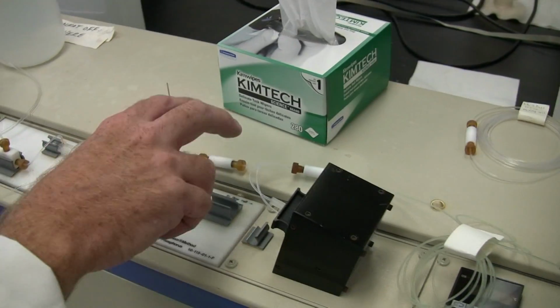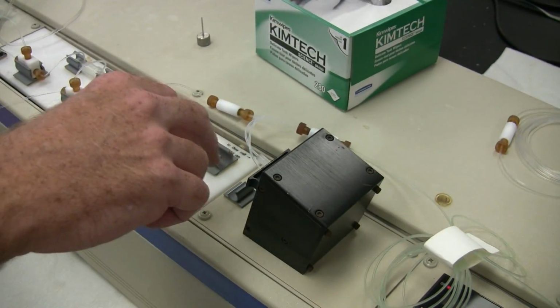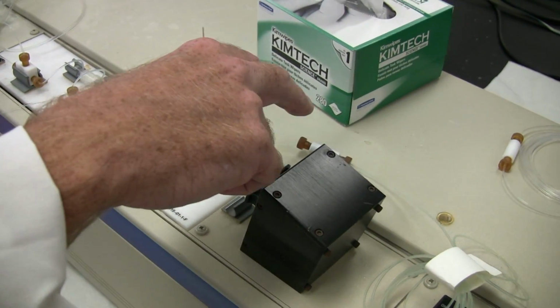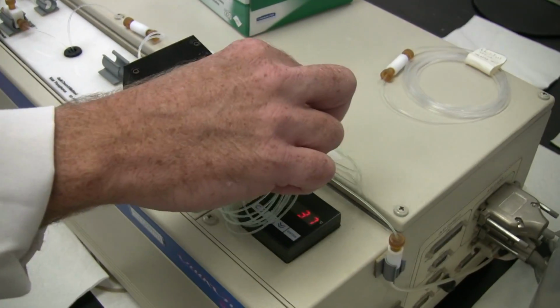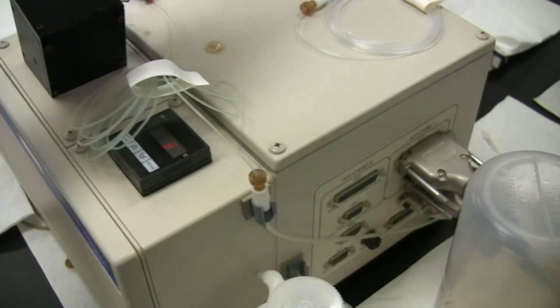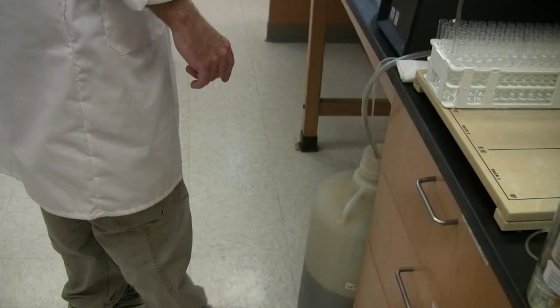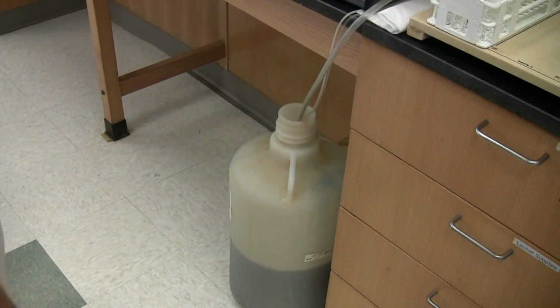The sample comes past the detector and has had this blue color develop. We come out, basically, to a waste line. The waste line traces back underneath the instrument and just comes to a jug. In our carboy here, we collect this waste because it is acidic. It's not anything hazardous as far as the chemical content. We just have to neutralize it to between, I think, 5 and 7, or 5 and 9, or whatever. We neutralize it and then we can just pour it down the drain.